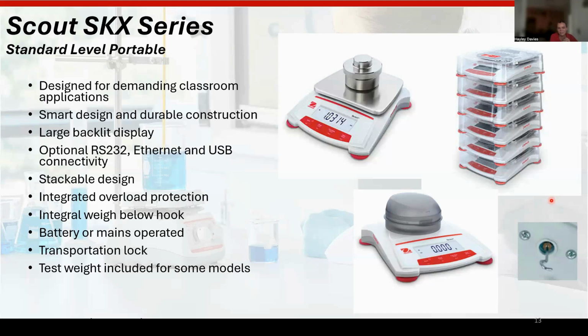You've got a large backlit display. They're easy to use. The overload protection, as I've mentioned, is 10 times the maximum capacity. The Scouts also have an integral underweighing or below-weigh hook, which is good for applications such as oscillation or any underweighing that you need to do. If you have Scout balances and you're not sure if you've got one, go back and check them. If you turn them upside down and look where the batteries go, take the battery case off, and if you look in the lid of the case, there is an under hook, and you'll get that with every single Scout balance.